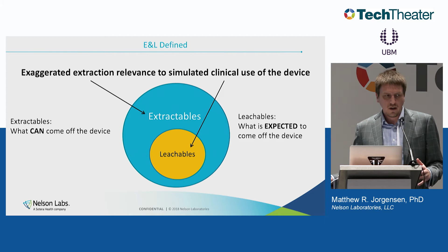And I think the reasons why you should consider using chemistry testing as an alternative to those biocompatibility tests are pretty clear. You save a lot of time and money right up front because it's a lot less expensive than running those bigger tests. You get really detailed results. So if you do a subacute or subchronic animal test and you fail, then all you know is that you failed and that you're in trouble, right? But if you do the chemistry testing and there's a problem, then you know what that problem is. It's localized to a certain chemical that you can then trace back and try to understand where it came from. It gives you a roadmap to solving the problem.